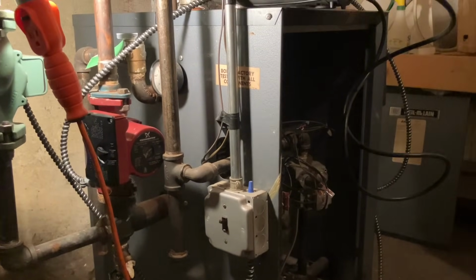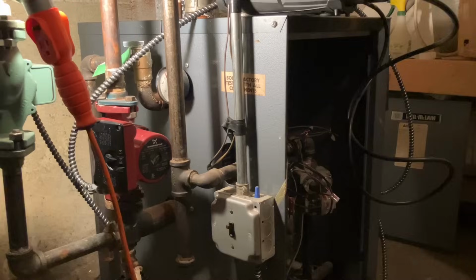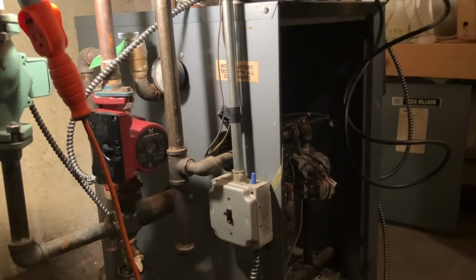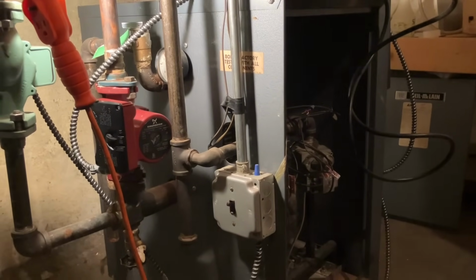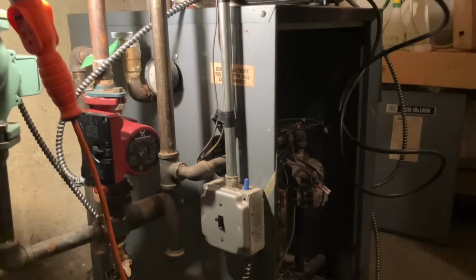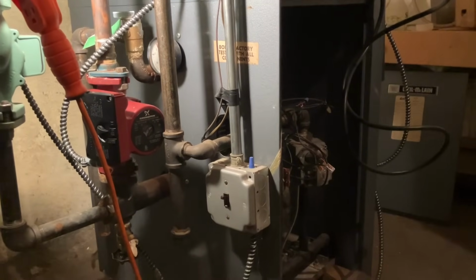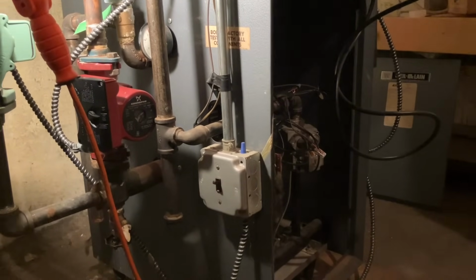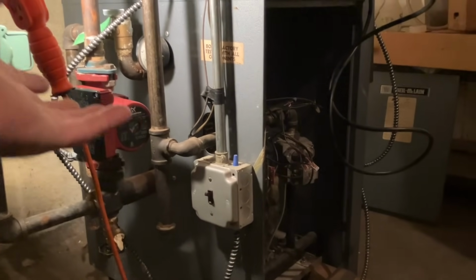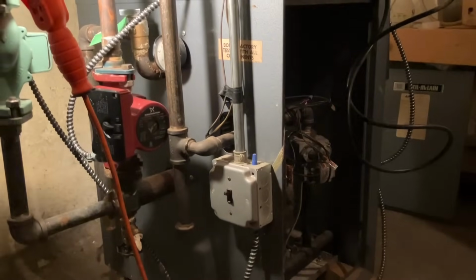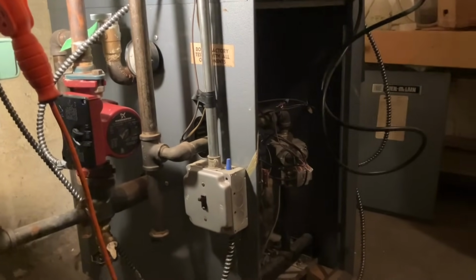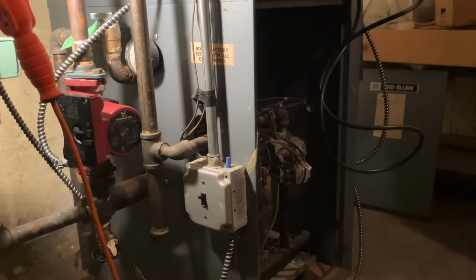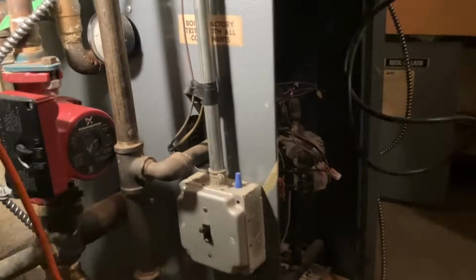However, you don't have a low temperature heating system in this home. You have a system with baseboard or radiators that needs 180 degrees of water, typically, to properly heat this home. Because back when this house was built in the 60s or 70s, right, grossly oversized systems were put in all the time. It didn't matter what size the boiler was because no one cared about the cost of energy, because energy was cheap until the embargo happened in the late 70s, right? But you need 180 degrees of water.